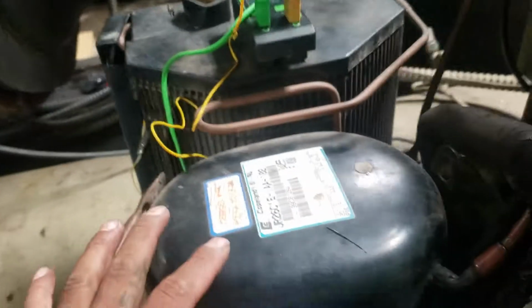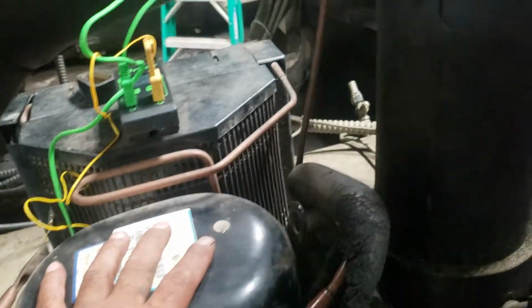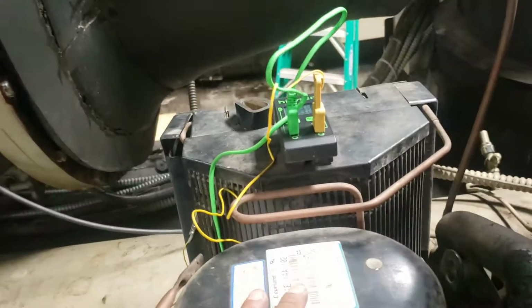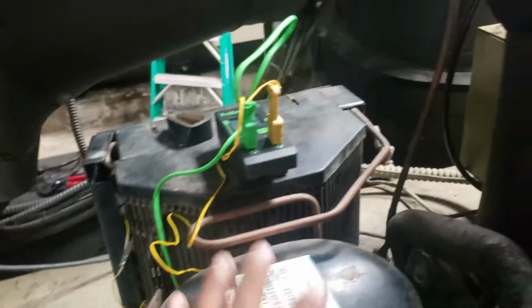And I'll take you around and show you the Purge unit itself. It's right here. This is the Purge tank. It's like the evaporator. And this is its own little refrigeration system. This is the Purge tank. It has nothing to do with the chiller. This is a whole different refrigerant. This is R134. That's R123. It's a low pressure.